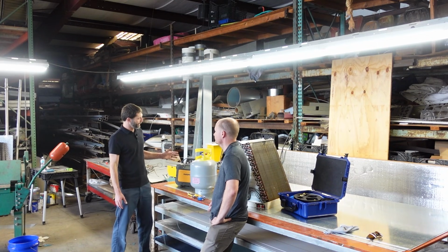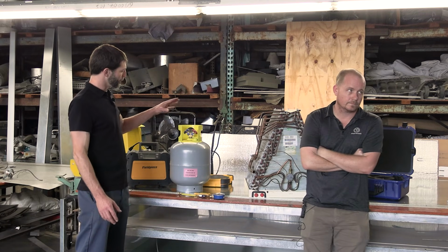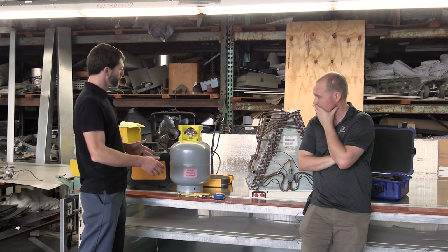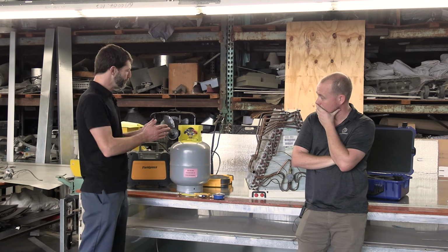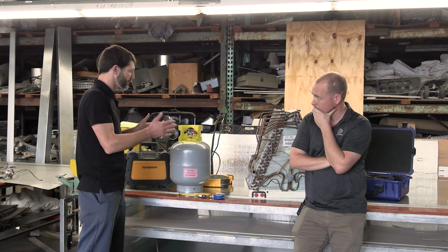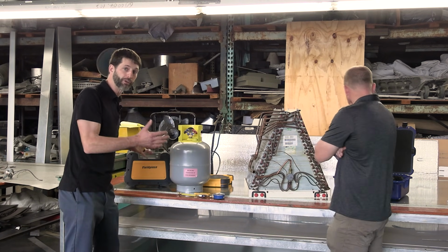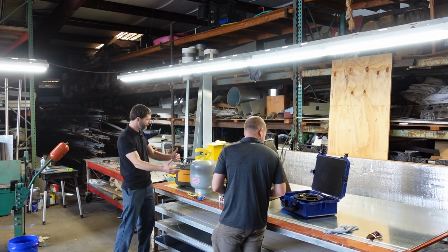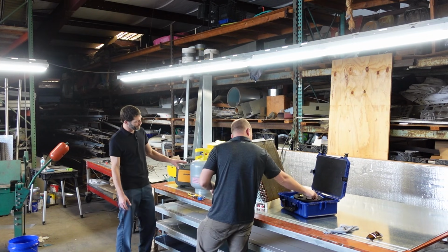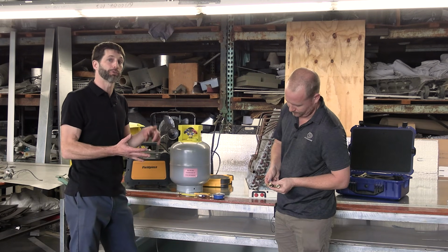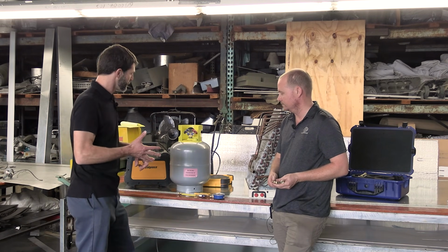Now, the other thing is that when you're hooking up your hoses to the system, you want to remove the valve cores. You want to remove any restrictions that are going to slow your recovery down. So you want to get all that refrigerant into this tank. You want it to be quick, but you also want to get all the refrigerant out of the system.